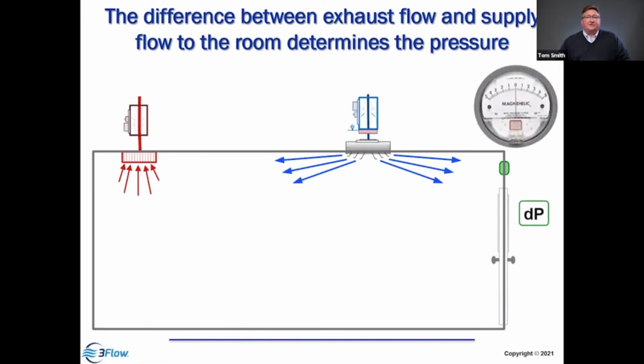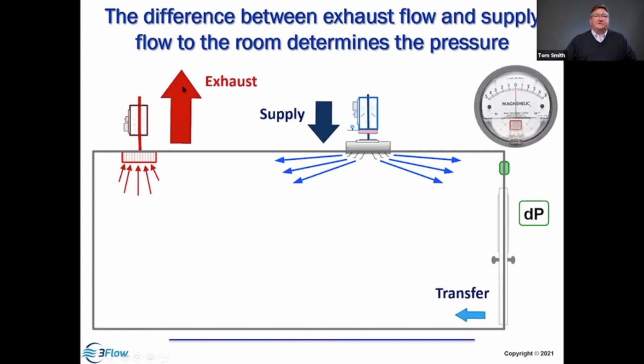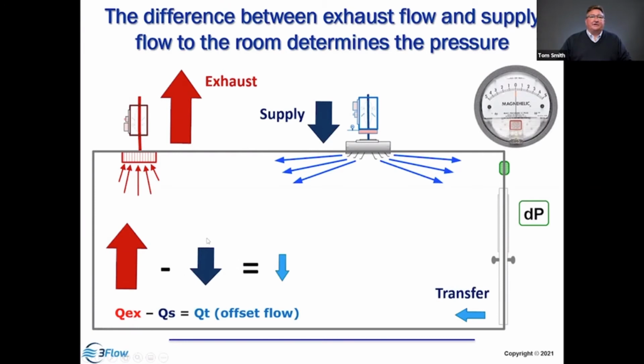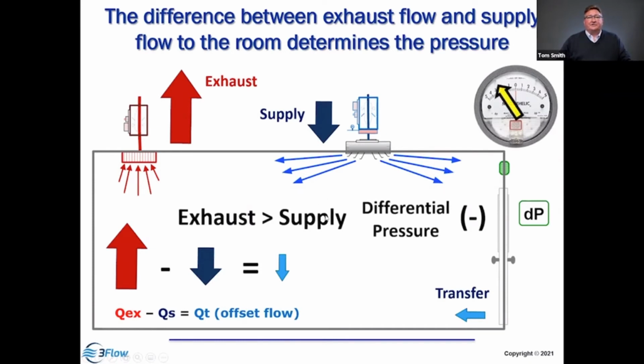So again, we look at our side view of the lab space, and we have some type of pressurization gauge maybe, and then we're looking at the total exhaust and the total supply. If the total exhaust from the space exceeds the supply, then the offset flow, exhaust minus supply, equals the offset. That's the airflow coming in from non-lab spaces and being drawn into the room. We're exhausting more air out than is being supplied, so it's sucking air into the room through all openings, typically underneath the door or around the door. And so when we look at this, we're saying that the exhaust exceeds supply, so this room is under negative pressure.